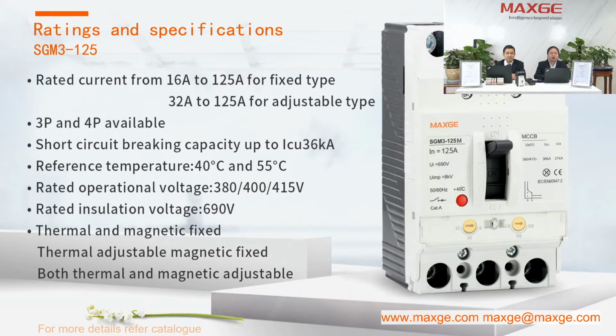The first one is SGM3-125 ampere, and we have 3 choices for this frame, as we introduced. First is the fixed type. Then the second is the only thermal adjustable but magnetic fixed type. The third one is both thermal and magnetic adjustable. The ratings differ between fixed and adjustable types. The fixed type is from 16 to 125 ampere, and the adjustable type is from 32 to 125 ampere. Yes, a big range, from 16 ampere. It is available in 3-pole and 4-pole.